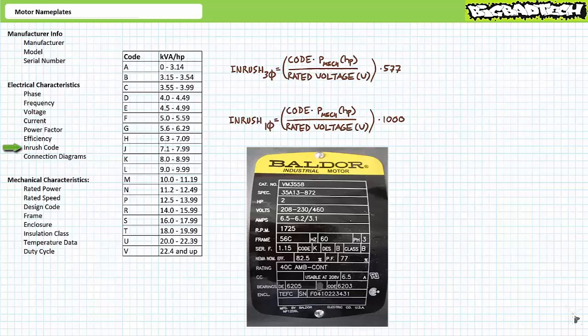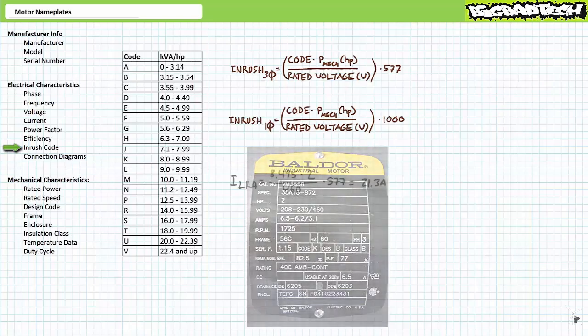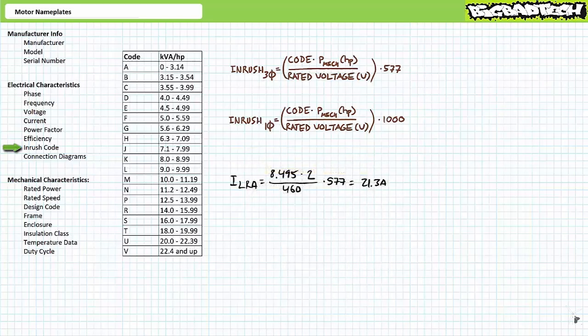However, the inrush code can give us a much more accurate result. Code K represents a constant of 8 to 8.99. So, aiming for the center of the range, say it's 8.495. Substituting this value, the mechanical power in horsepower, and the rated voltage into the equation demonstrates we would expect to see an inrush of 21.3 amps in the high voltage configuration. Again, luckily inrush doesn't last for long, but you've definitely got to take a 21.3 amp surge into account.